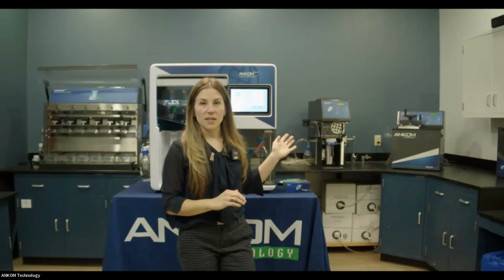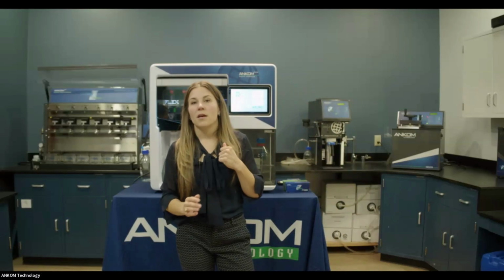And then for the XT15 extractor, you would weigh your samples. The extractor itself is about an extraction time of 30 to 60 minutes, usually more on the lower end. And then for the Delta, you would weigh your samples, again depending on your technician's skill, 15 minutes maybe, and put it in the extractor. Is there a difference in time for crude versus detergent runs? Crude is about half an hour longer. Okay, so how long is the detergent run? An hour and a half. So you're looking at anywhere from an hour and a half to 2 hours when it comes to the fiber runs.